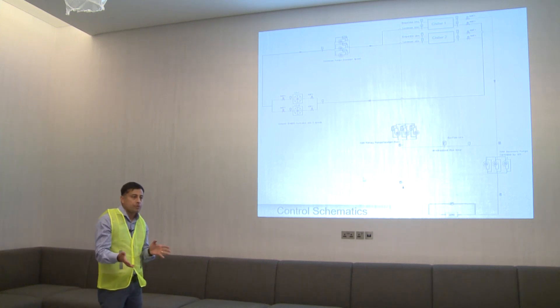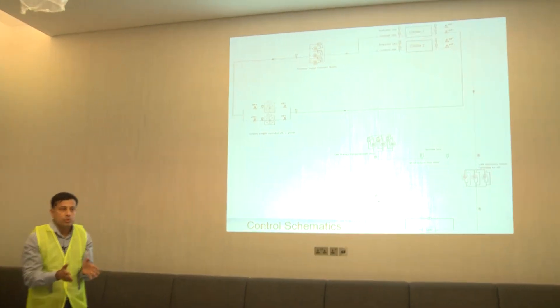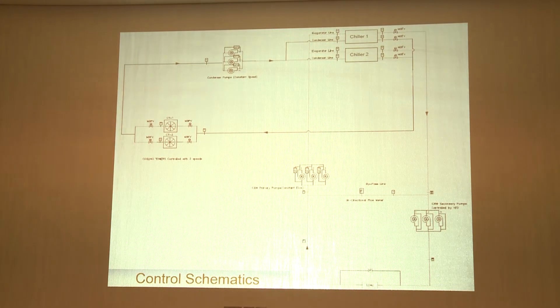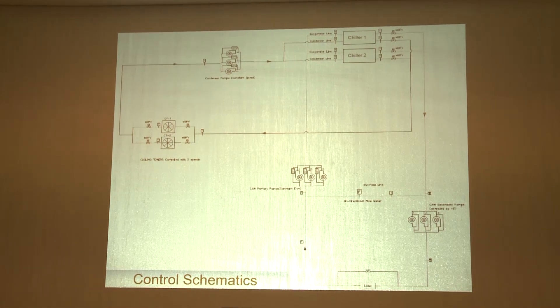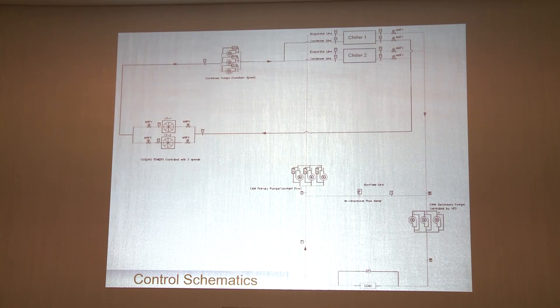For example, if this room is designed for 22°C and you deviate from the design chilled water temperature, you will not achieve 22°C. With 5.5°C supply, the FCU may reach 22°C within 5 minutes. But if you deviate to 7°C, it may take 15 to 20 minutes to achieve the design room temperature. This is the consequence of deviating from the set points.